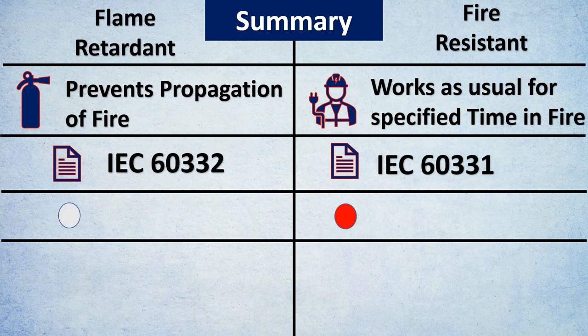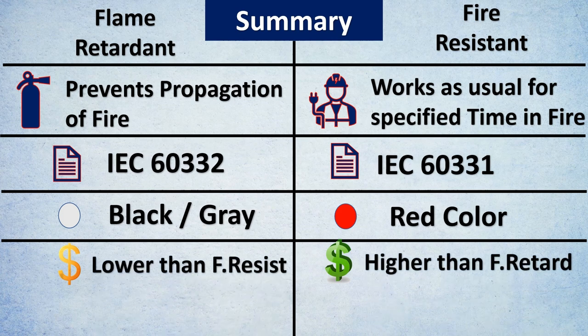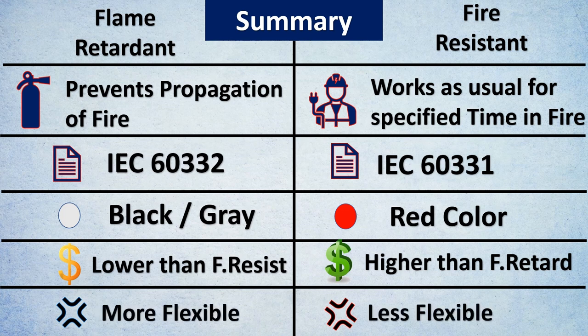Flame retardant cables are usually grey or black in color, while fire resistant cables are usually preferred to be red. These are thumb rules and depend on the design basis and client requirements. In terms of cost, flame retardant cable will have lower cost compared to fire resistant cable due to the insulation differences. In terms of flexibility, flame retardant cables are more flexible while fire resistant cables are comparatively less flexible.